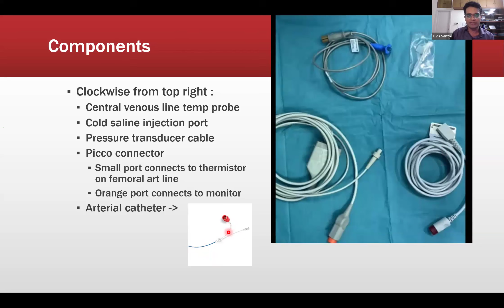The main difference is, as you can see here, once a cannula is done, you have two cables. One is the normal port, which you connect to the transducer, which you can see on the right. And this transducer is connected with a cable to the monitor as usual. So this is the usual pressure, a pressure transducer as per normal. Only thing is you want to use the one given with the PiCCO set, because it's going to have a higher resolution. So you connect it, aspirate and flush it, and zero the lines as usual.